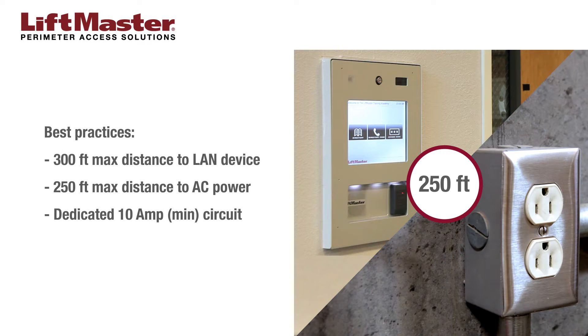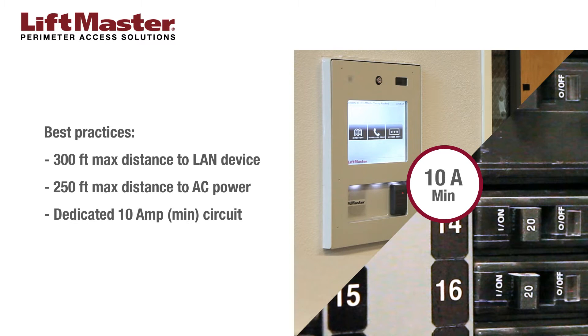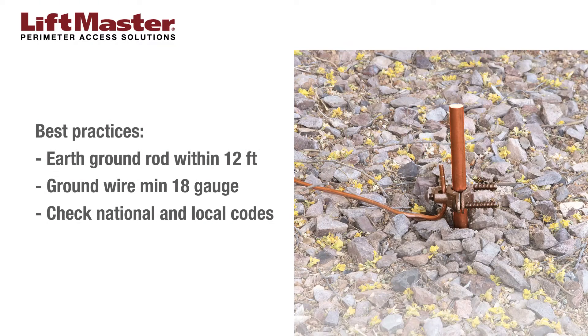Power the IPAC using a dedicated 120-volt AC outlet located within 250 feet of the access control panel. This outlet should be wired back to its own circuit breaker with a minimum of 10 amps. The IPAC must be grounded to a good ground source, such as an earth ground rod, in accordance with local building codes. The ground source should be located within 12 feet from the IPAC. Use ground wire that is a minimum of 18 gauge and keep the ground wire as straight as possible.